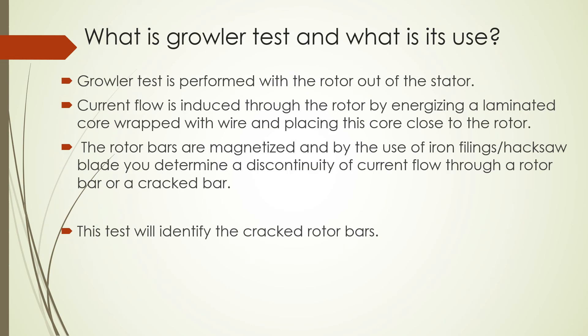The tenth question: what is the growler test and what issues does it identify? The growler test is performed on the rotor out of the stator. Current flow is induced through the rotor by energizing a laminated core wrapped with wire and placing this core close to the rotor. The rotor bars are magnetized and, using iron filings or a hacksaw blade, you can determine the discontinuity of current flow through the rotor bars or identify a cracked bar. This test identifies cracked rotor bars.